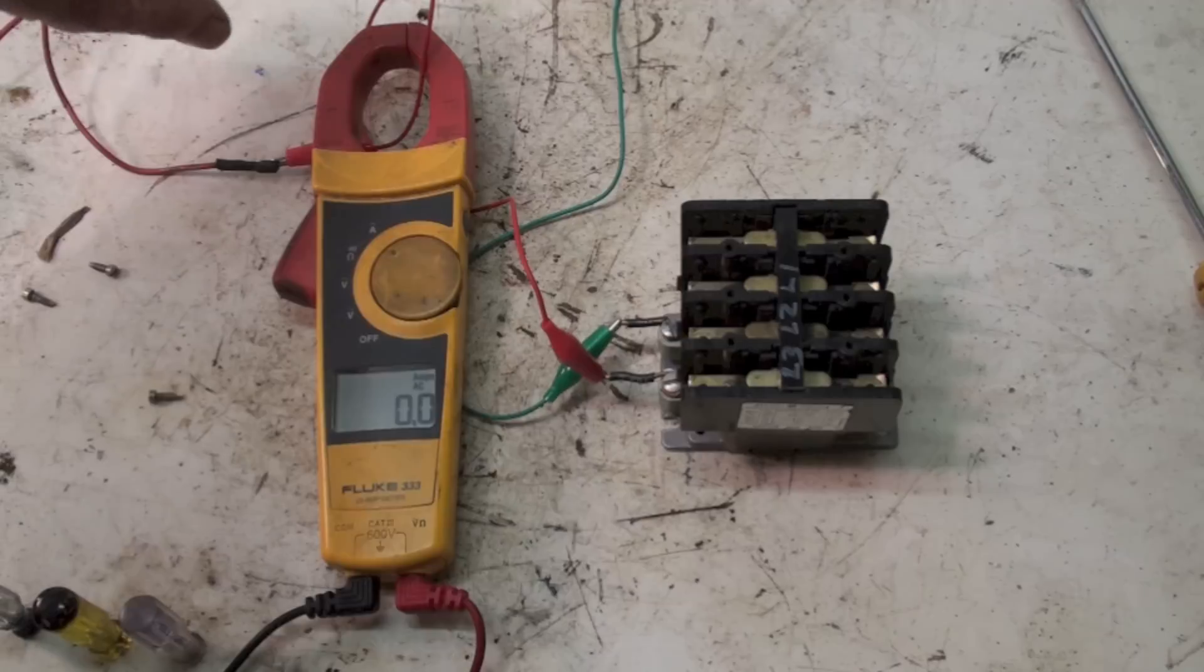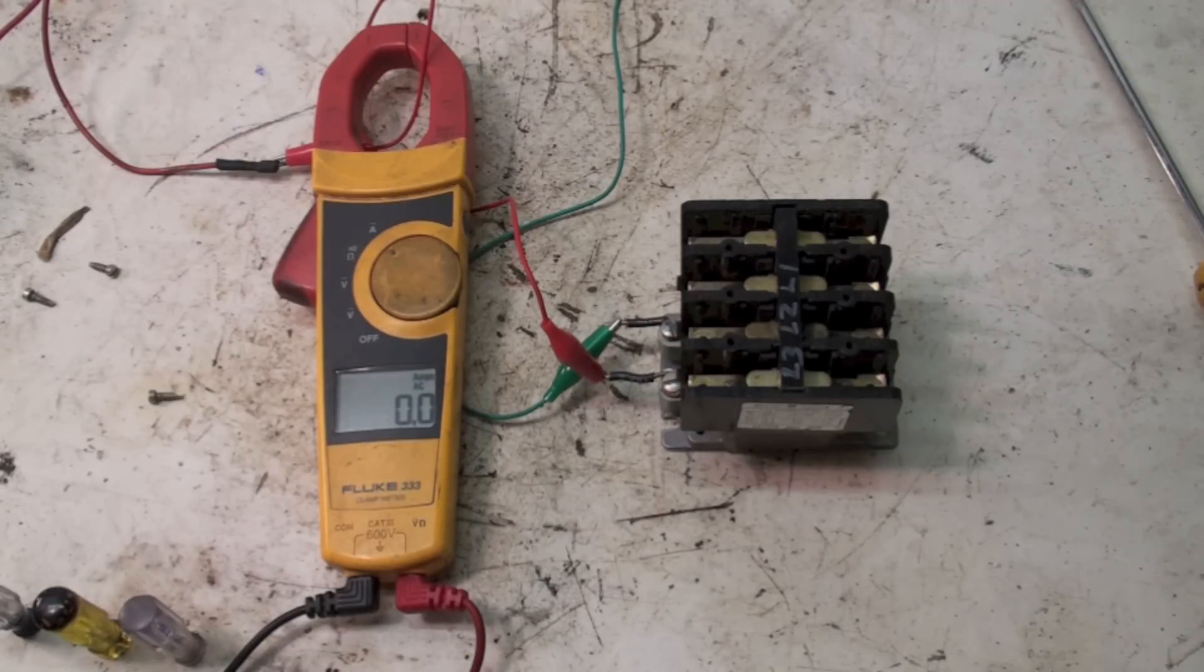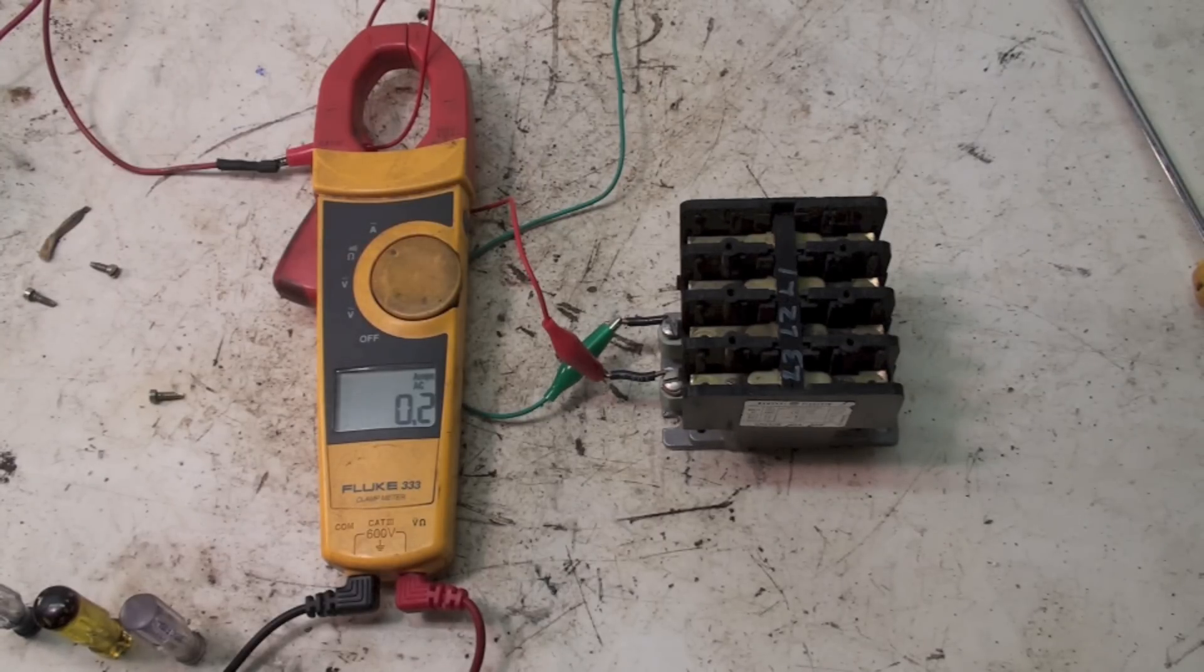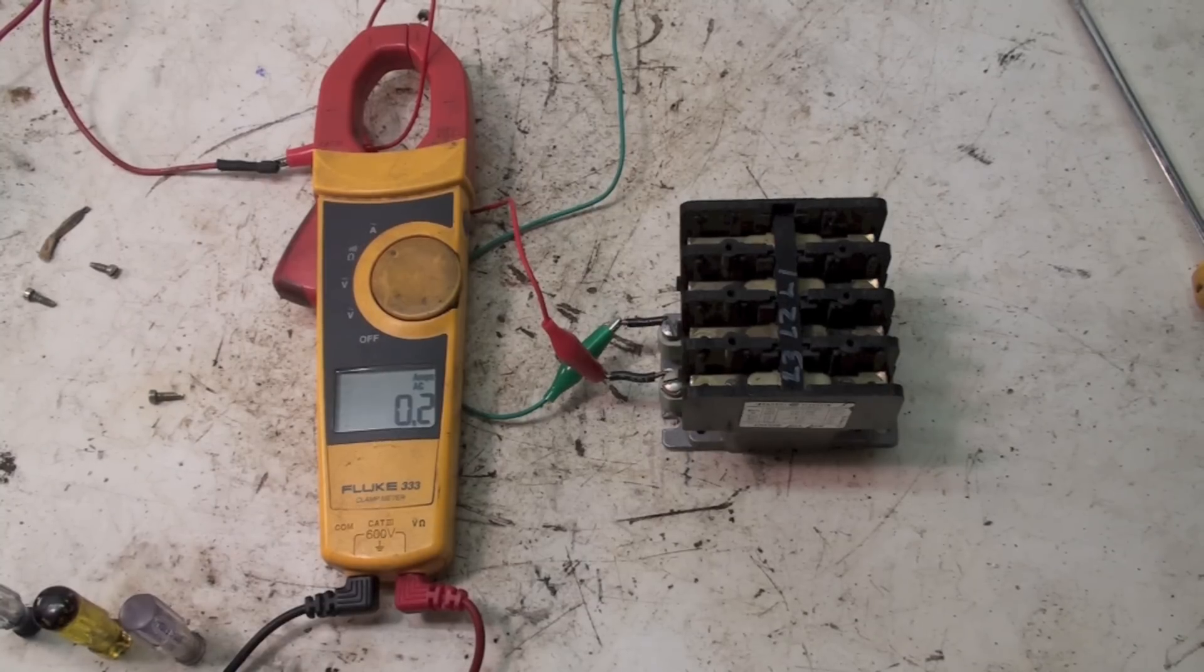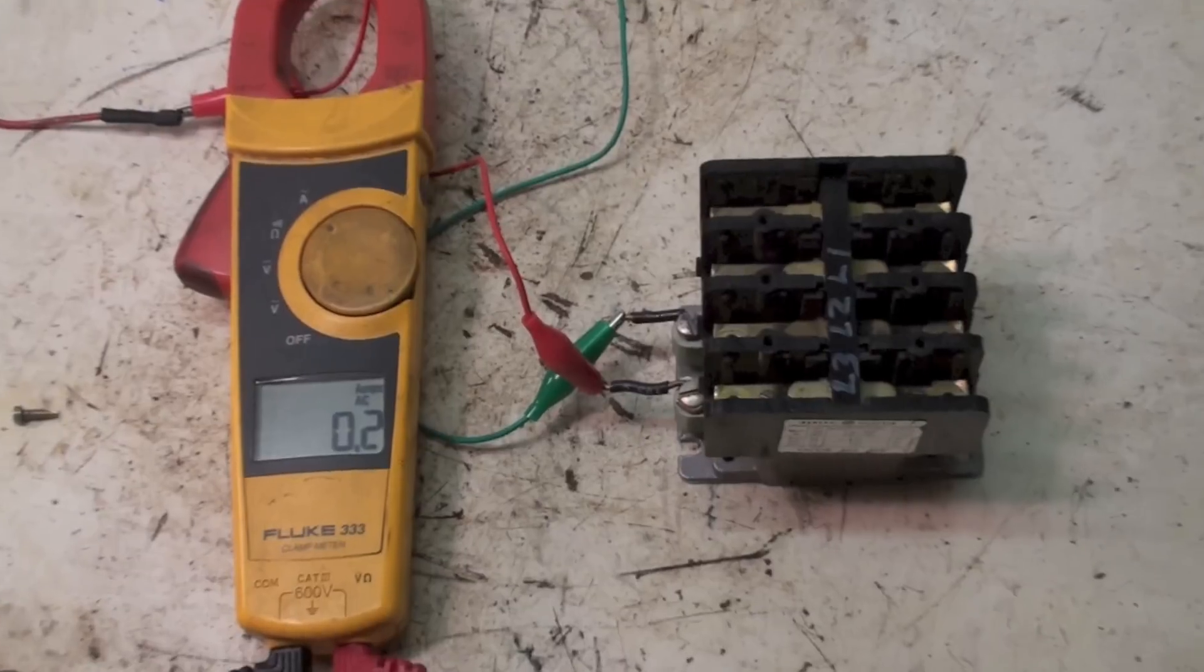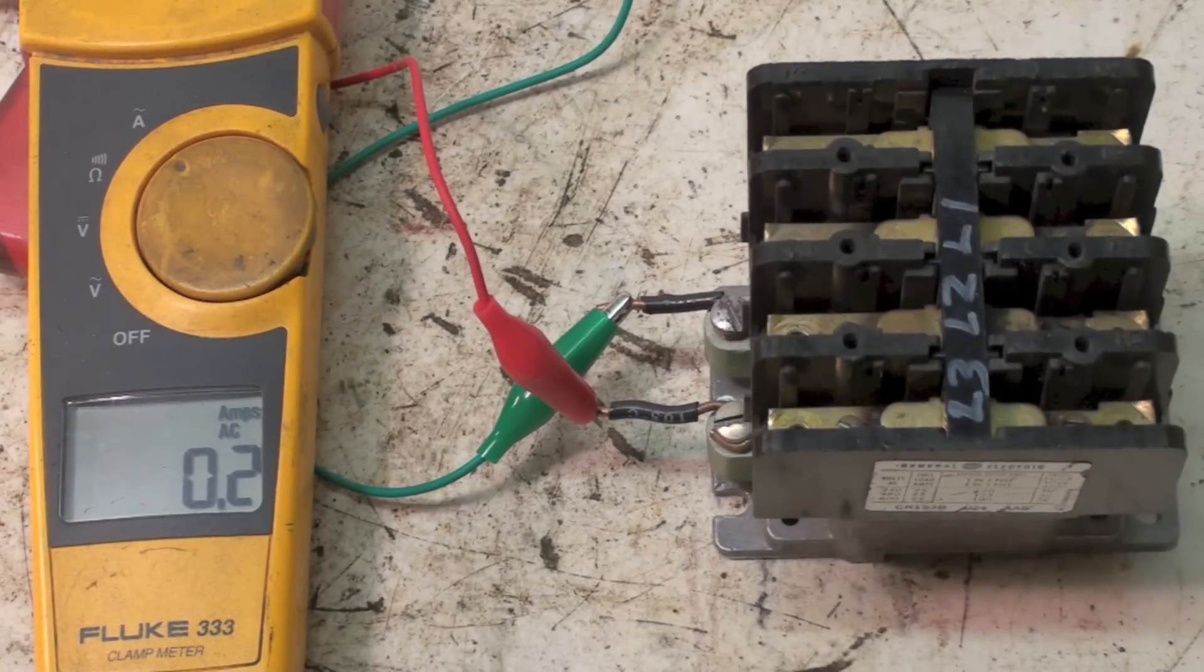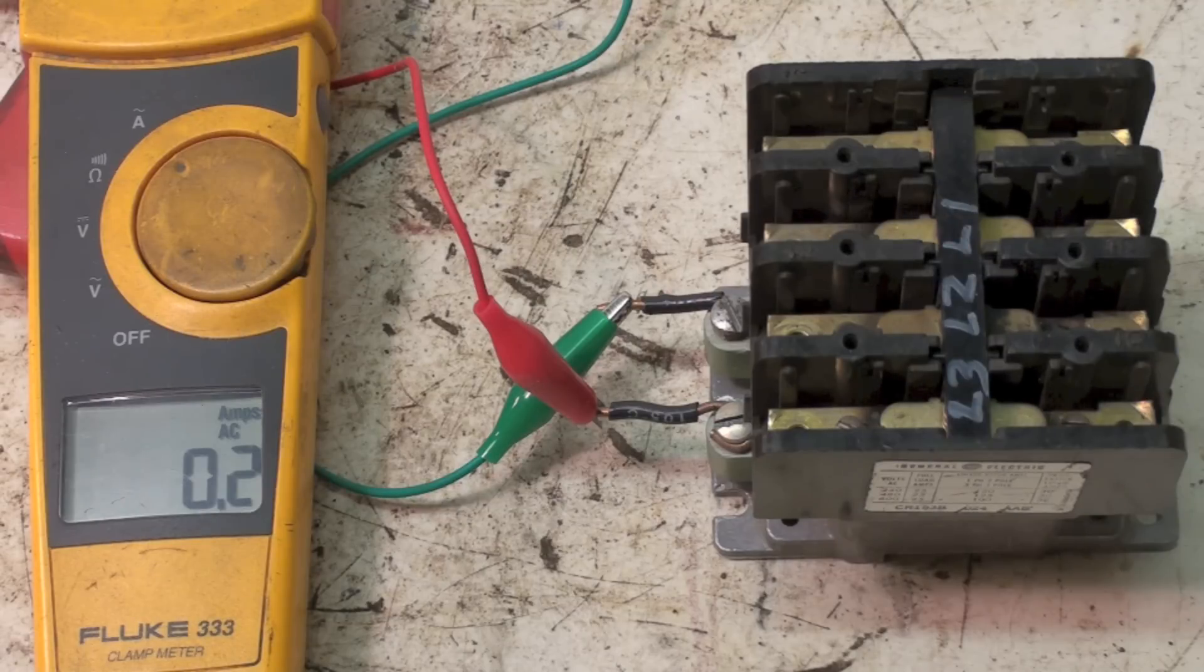What I want to demonstrate is what happens when different things happen to this coil. Right now it's normal, everything's fine. The contactor will pull in like it should. If you notice we've got about 0.2 amps and it pulled in normally, just like it should. Now let's go ahead and shut it off.